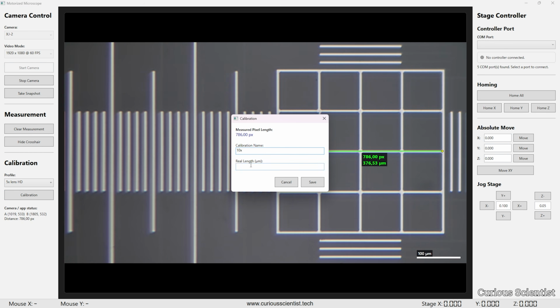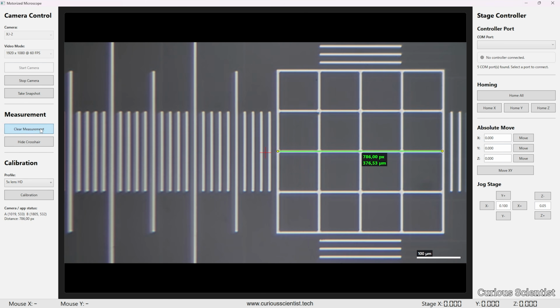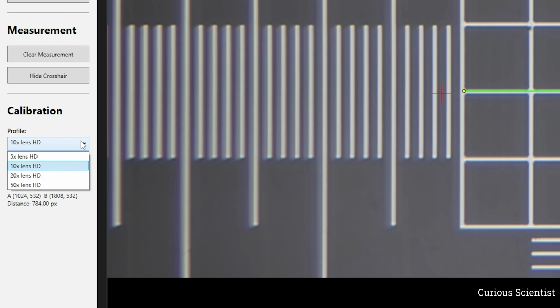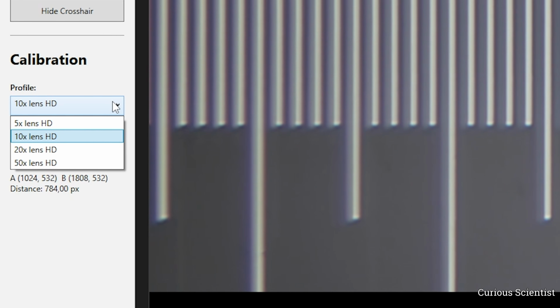Then, the real length in micrometer units can be entered. Afterwards, the calibration becomes available in the drop-down list under the calibration profiles, and when the proper calibration is selected, the measurement line will show the correct distance, and the scale bar at the bottom right corner will be rendered correctly as well. I created the calibration profiles for all 4 lenses in my microscope: 5 times, 10 times, 20 times, and 50 times magnification.